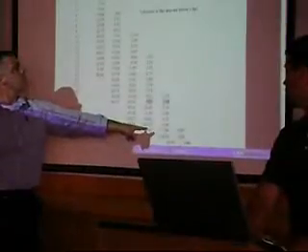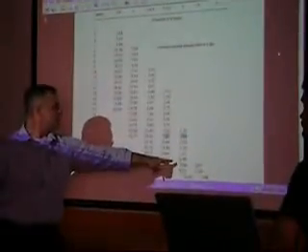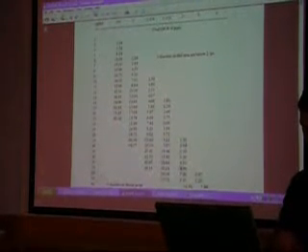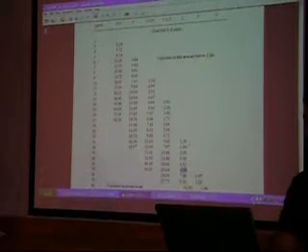And you see here also that the higher the flow rate, this is the flow rate column, the higher the friction. See how at 50 GPM, 1.5 inch, 2 inch, look at the difference per 100 feet. So that's another reason not to use 1/4 inch holes, right? 1/4 inch holes mean higher flow rate.